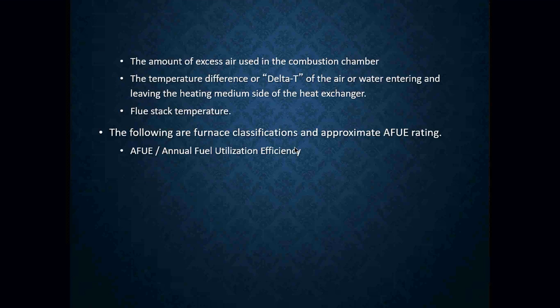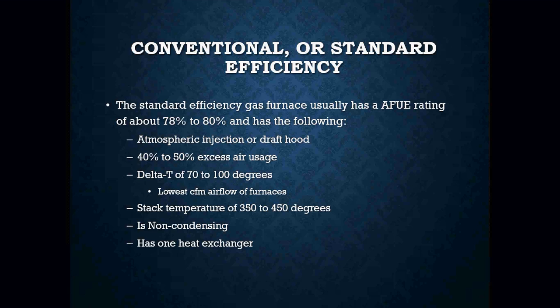The amount of excess air used in the combustion chamber also will affect furnace efficiency. The temperature difference, or delta T, of the air or water entering and leaving the furnace is also going to affect it, and how hot your flue stack temperature is. The following are furnace classifications and approximate AFUE ratings. Again, AFUE stands for annual fuel utilization efficiency.